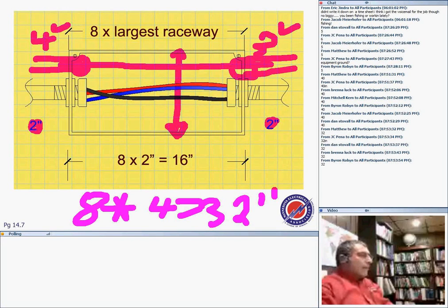I cannot find the height of this box based on this information. You can probably guess. If I would guess, I would say, okay, this is just 2 inches, right? I need the space for the 2 inch conduit, plus I need space for the 3 inch conduit, the worst scenario. That will get me 4 inches, right? Plus lock nuts and enclosures and so forth. So that's basically 4 inches you need. And how far will you go from the edge? I would say you might need, from both sides, half an inch at least, an inch plus half an inch plus another inch between.